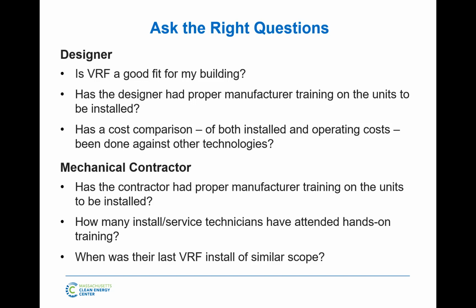So one part we kind of skipped here was things you should be asking. I see this all the time where building owners will come to me and say, well, here's this well-known mechanical contractor that can point to 20 VRF systems they've installed with references, and they're 10% more than this guy who has no record of training, never heard of him before, and they're eager to start the job. And you're going to spend a lot more than 10% of the job cost off that savings to go back and fix refrigerant leaks, because that's one of the differentiators between a contractor who's trained in the equipment, trained in the proper installation, and then testing procedures to make sure that system's tight and leak-free and clean.